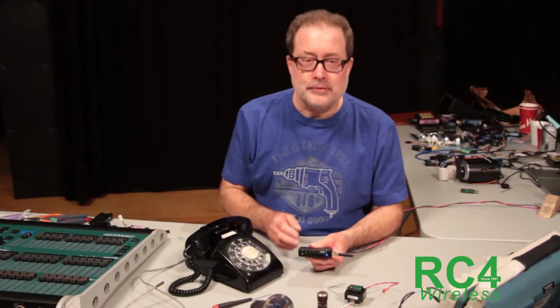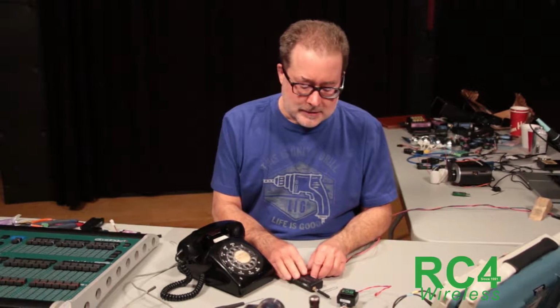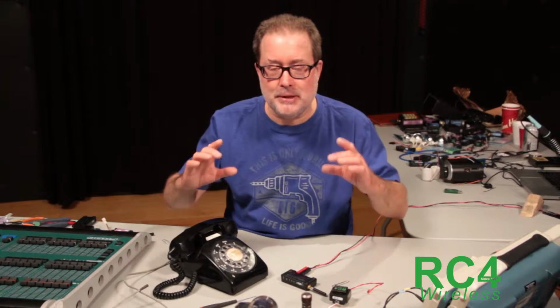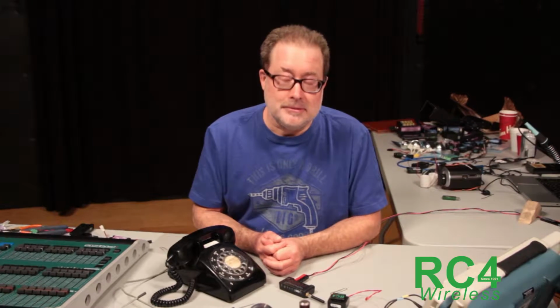Now I'd like to make this telephone ring on DMX channel 25, using Enhanced OneTouch. This is a little feature kind of buried in the documentation. All of the dimmer curves available are hidden at the low end of the OneTouch process. Where you've normally set it at 30%, 50%, and so on for the common curves, you've also got a tighter matrix of curves starting at a level of 20. So a DMX level of 20 gives you ISL slow, 21 gives you ISL fast, 22 gives you linear, and so on, through curves you can't get other ways. A value of 30 selects the AC wave generator.